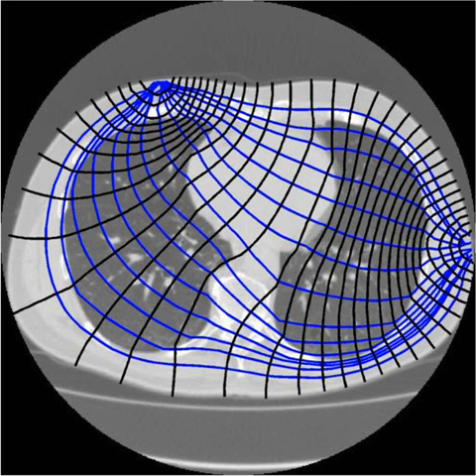The V5R is a high-performance device, based upon a voltage-voltage measurement technique, designed to improve process control. The high frame rate of the V5R means that it can be used to monitor rapidly evolving processes or dynamic flow conditions. The data it provides can be used to determine the flow profile of complex multiphase processes, allowing engineers to discriminate between laminar, plug and other important flow conditions for deeper understanding and improved process control. When used for concentration measurements, the ability to measure full impedance across a wide range of phase ratios means the V5R is able to deliver considerable accuracy across a wider conductivity range compared to other devices.